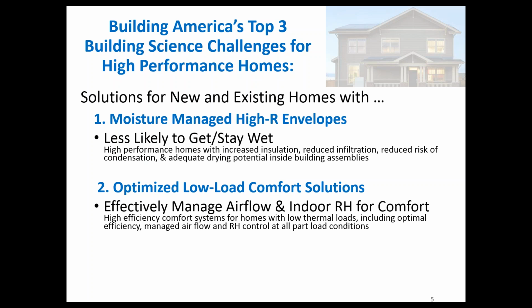We use a lot of energy achieving comfort, and it's not necessarily about the HVAC system, which people tend to think of only as the visible box in your house. So we're trying to change the language. The low load part means that as our envelopes get more efficient, if we're successful at the first challenge, then the HVAC systems cannot be designed and operated as they used to, because the loads won't be high enough. They won't run very often. They may not actually need enough cooling or heating such that the airflows go down, and the dehumidification that needs to happen in hot and humid conditions doesn't happen because you're not running the comfort system often enough.